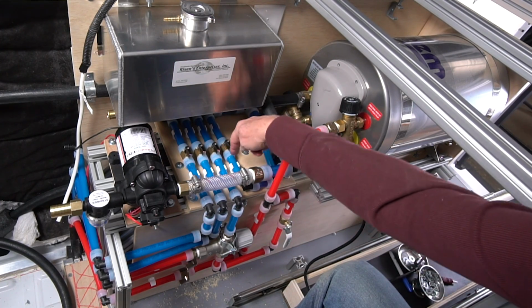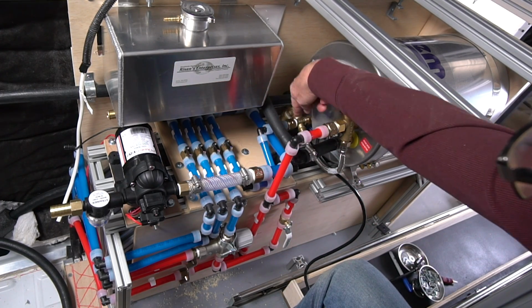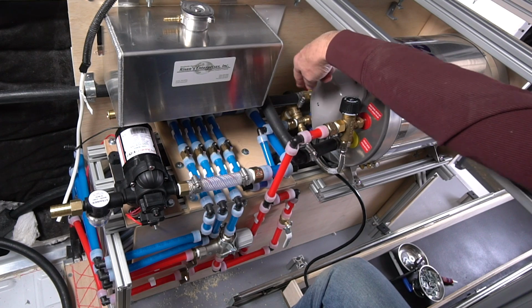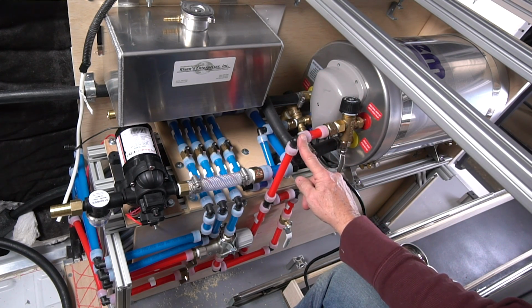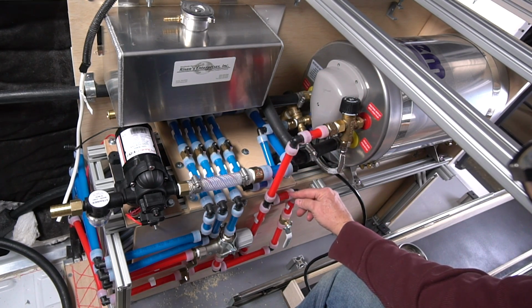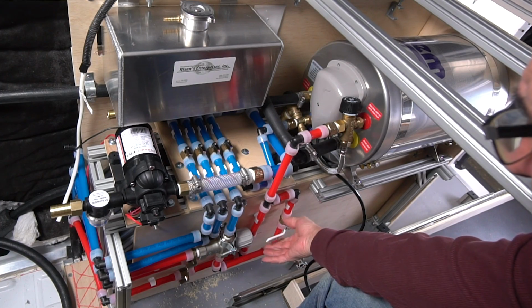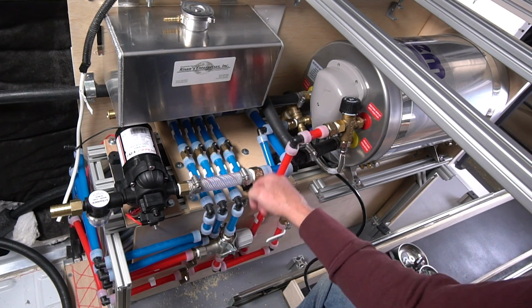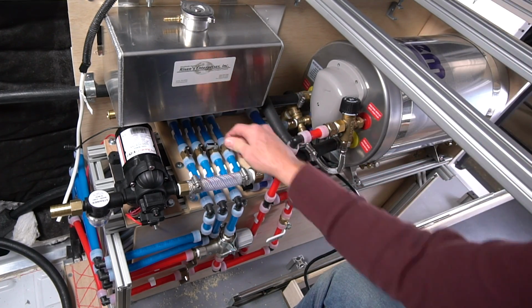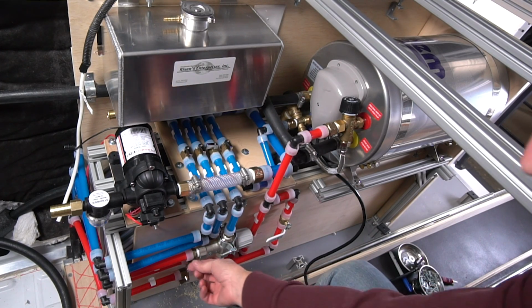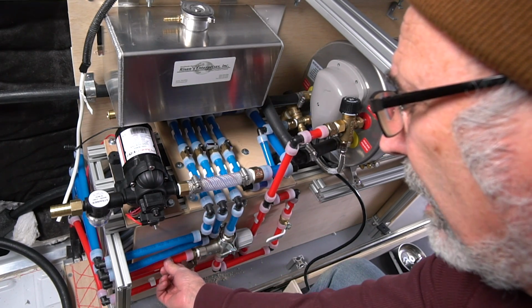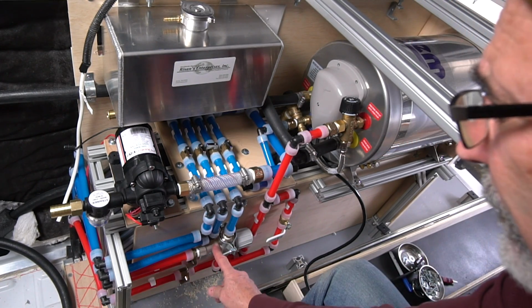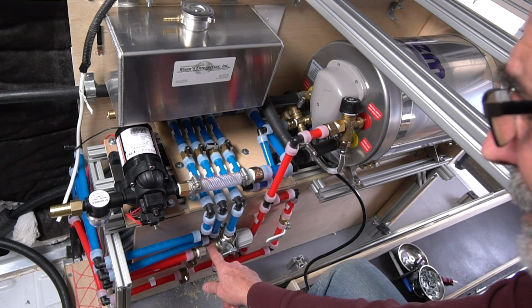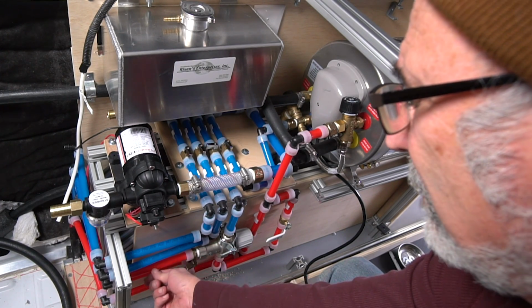The fourth line comes around and goes into the water heater. That's the cold water into the water heater. The hot water comes out here. The hot water comes down and it branches off. This is a valve that would isolate the mixing valve for the outdoor washdown. Now I could have put one valve to shut down the washdown here, but what if this is the failure? What if the mixing valve failed? This valve isn't going to help you.